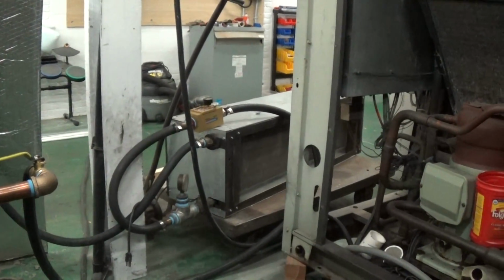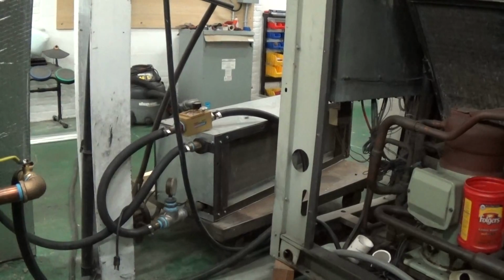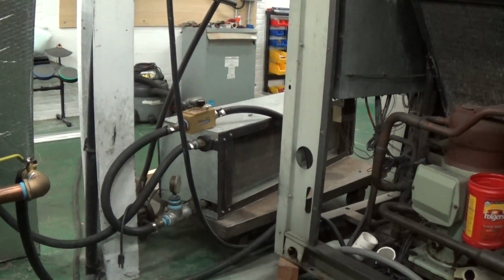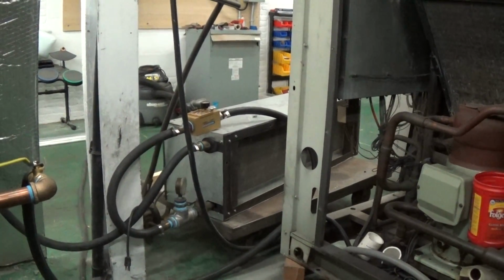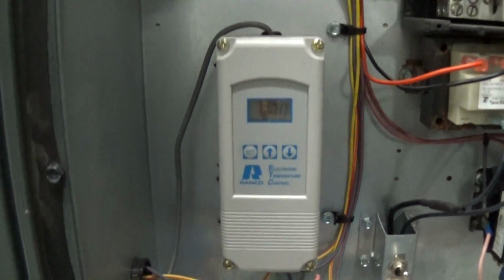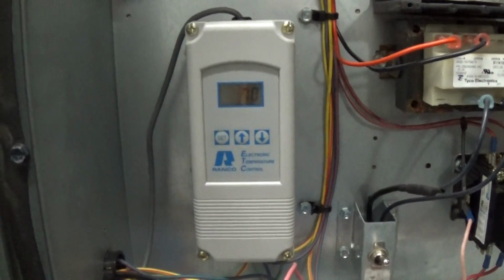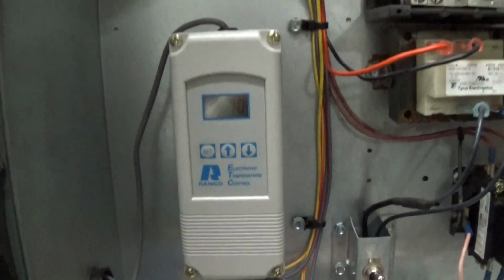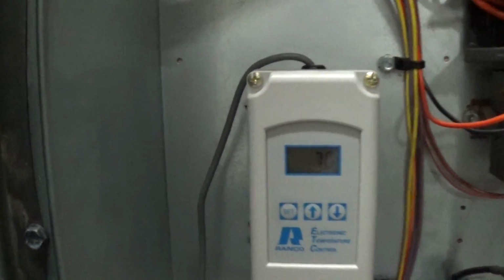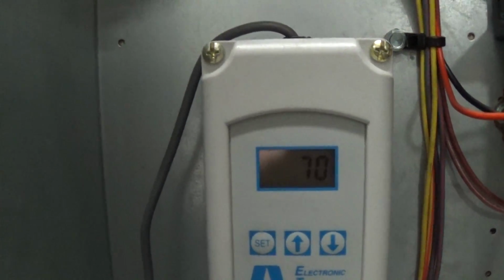I'll talk about that in a bit. When we've been testing it over the last week, we've actually been running it through this air handler here, which creates about a 3 or 4 ton load, just to help us get some additional run time in this shop testing setting. The nice thing about the ChillKing chillers, or any chiller using a Ranco, is how simple it is.